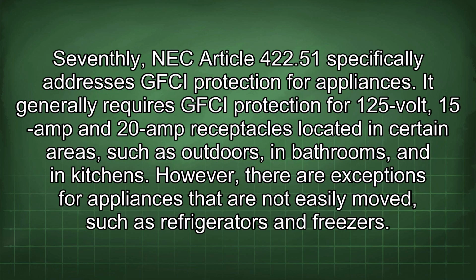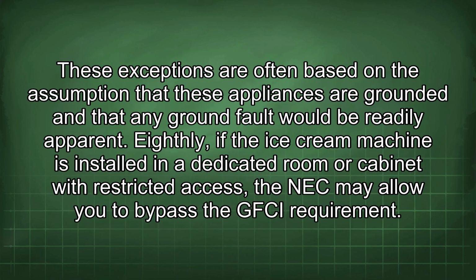Seventhly, NEC Article 422.51 specifically addresses GFCI protection for appliances. It generally requires GFCI protection for 125 volt, 15 amp and 20 amp receptacles located in certain areas, such as outdoors, in bathrooms, and in kitchens. However, there are exceptions for appliances that are not easily moved, such as refrigerators and freezers. These exceptions are often based on the assumption that these appliances are grounded and that any ground fault would be readily apparent.